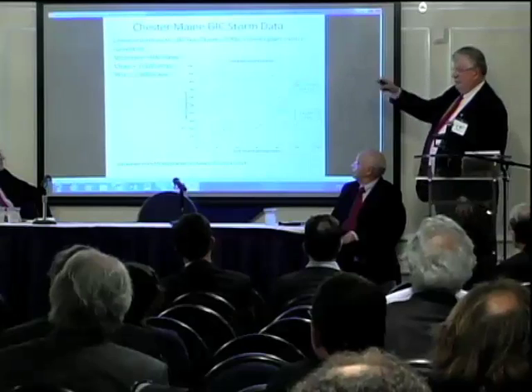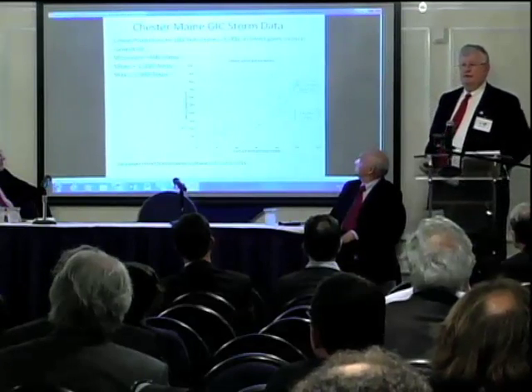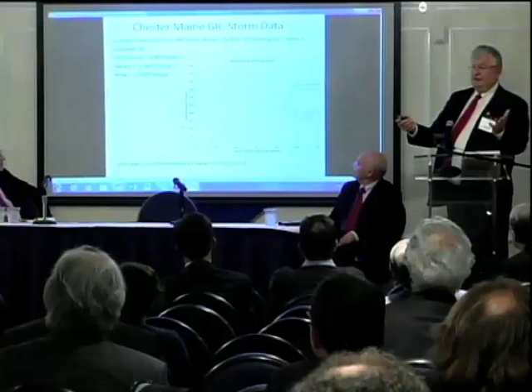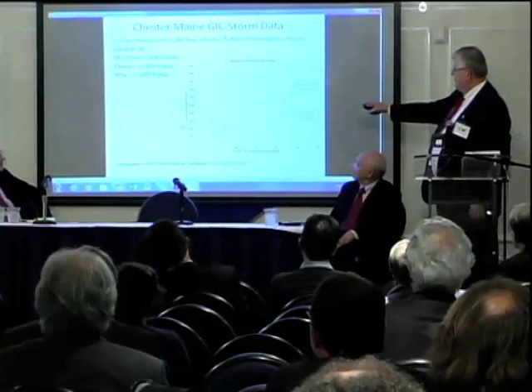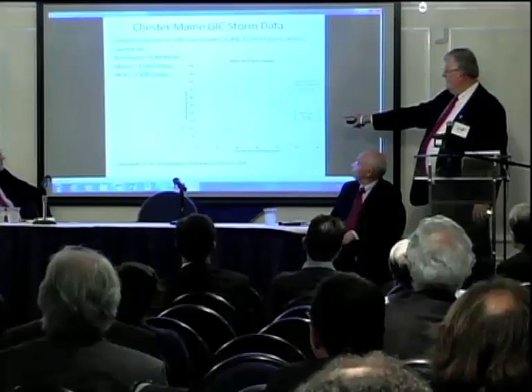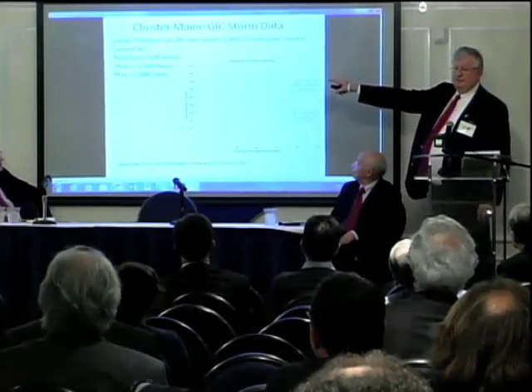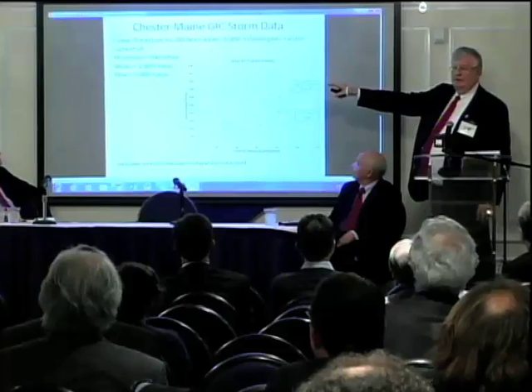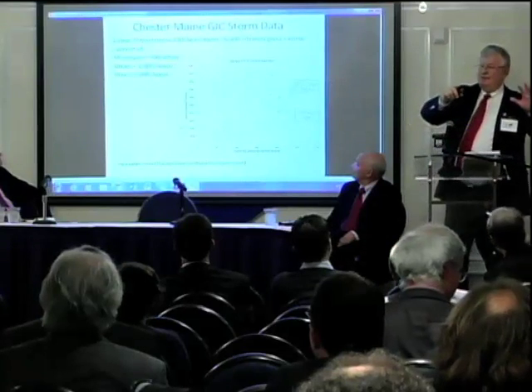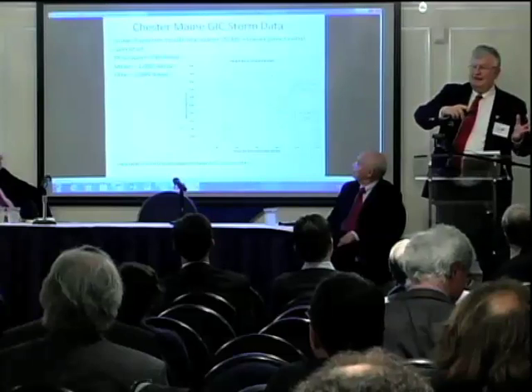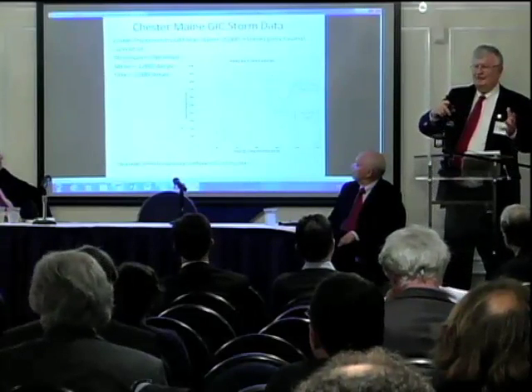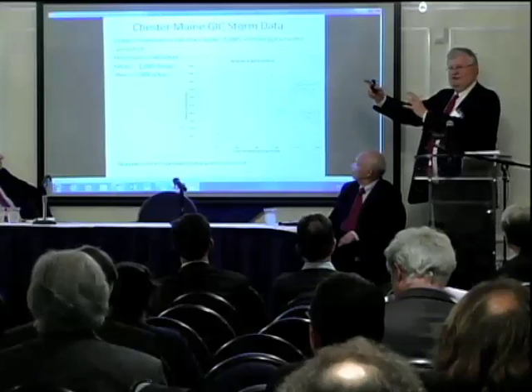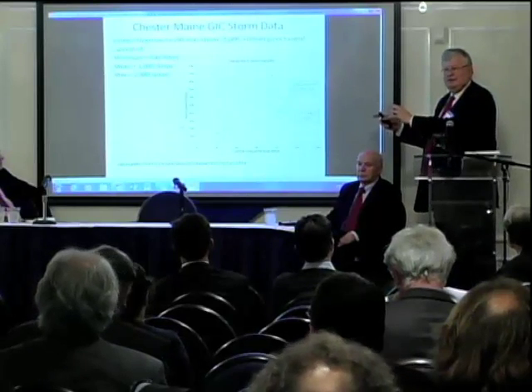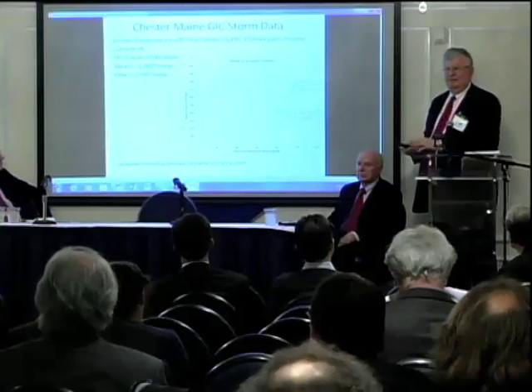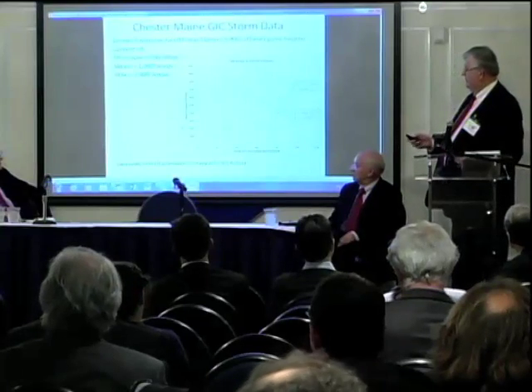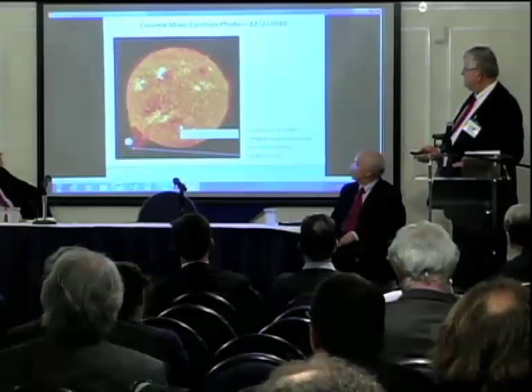So if you ramp that up to 5,000 nanotesla per minute for a 100-year storm, you multiply that by 20. You're going to get 2,000 amps in the neutral. Remember what we were talking about for harmonics at only 100 amps. And remember what Louis Marti just said, you'll have damage to rotors at 50 amps in the neutral. So we're suggesting this is a pretty serious issue.